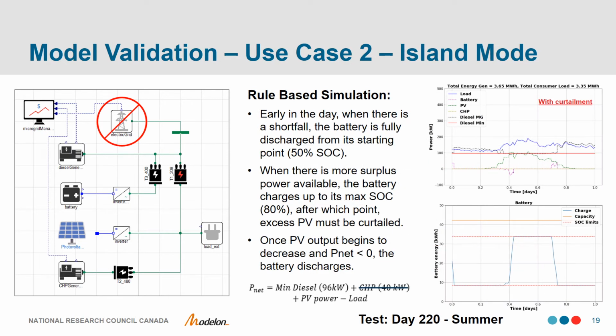Looking at the battery chart in the bottom right, you can see how the battery responds in the presence of surplus power. When there is surplus power available, the battery charges up to its maximum state of charge, after which point excess PV must be curtailed. Once the PV output begins to decrease and the net power is less than zero, the battery is able to discharge and supply all the stored power back to the microgrid.